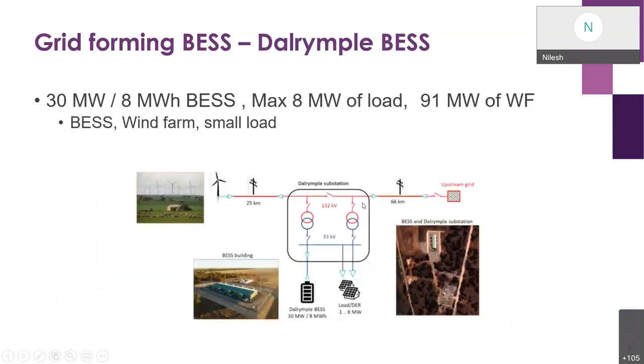Okay, so let's jump into the grid forming batteries. The first one of the rank is the Dalrymple BESS battery. Dalrymple BESS is the first transmission connected grid forming battery, as far as we know, installed in the National Electricity Market of Australia. It's connected at the end of a long, radial 132 kV line alongside 91 megawatt of wind farm and a local load of approximately 8 megawatt. This area is exposed to lightning and outages, and the installation of the battery improves the reliability of the network. So we call this a non-network solution. This battery also participates in the frequency control market.